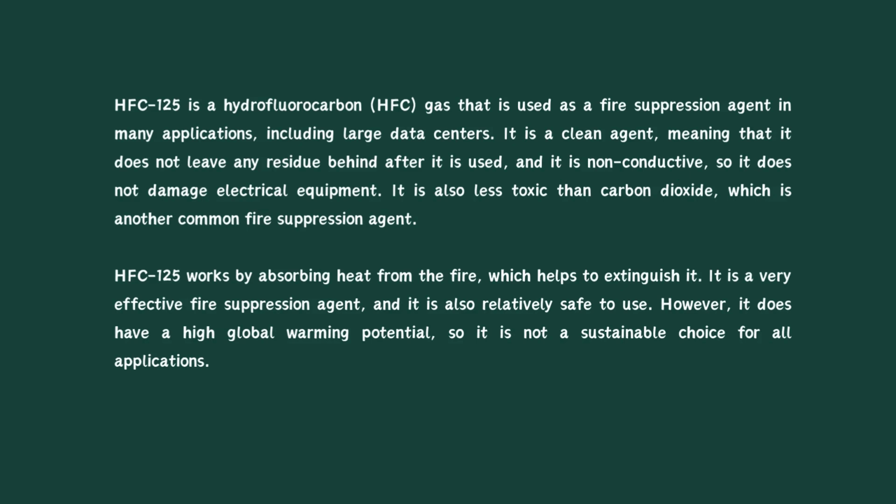It is also less toxic than carbon dioxide, which is another common fire suppression agent. HFC 125 works by absorbing heat from the fire, which helps to extinguish it. It is a very effective fire suppression agent, and it is also relatively safe to use. However, it does have a high global warming potential, so it is not a sustainable choice for all applications.